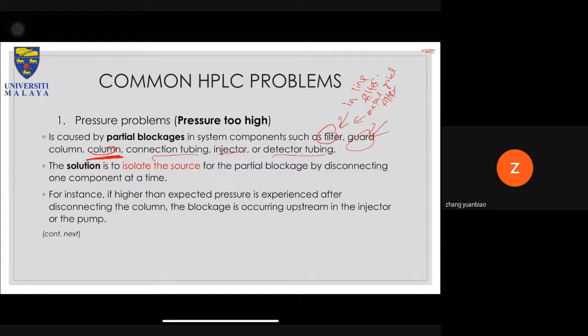Okay, so the first thing that you do is you want to isolate the source of the high pressure. As I mentioned, you normally start off near the detector and then move backwards. For example, if you run your pump at say 10 mL per minute, and the back pressure given is 5,000 psi, what you might want to do first is detach the last tubing connecting the column to the detector.